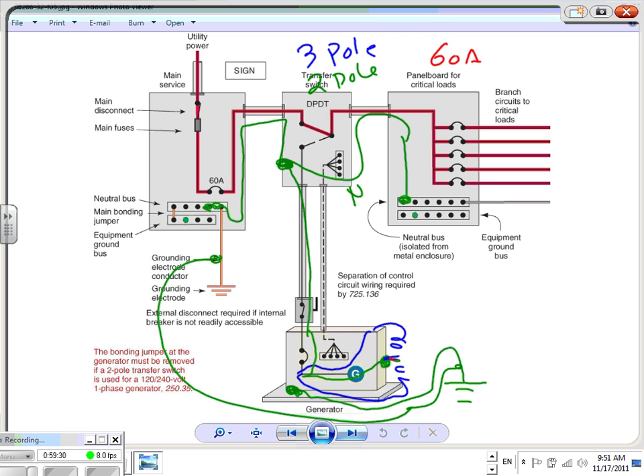Any questions? I want to bring to your attention, Rob, my friend, look at this. What is this? Disconnect. If you have a permanently installed generator, you need a disconnect within sight of the building. So you have to put a disconnect right next to it, if it's outdoor, within sight of the building, right? Do I need a disconnect inside the building? No, you don't. As you enter the building, this transfer switch could be in your basement. You do not need a disconnect for it. You go directly to the switch. You don't need a disconnect to this panel, obviously. The only disconnect that can disconnect this panel directly is this switch here, this one, or this one.